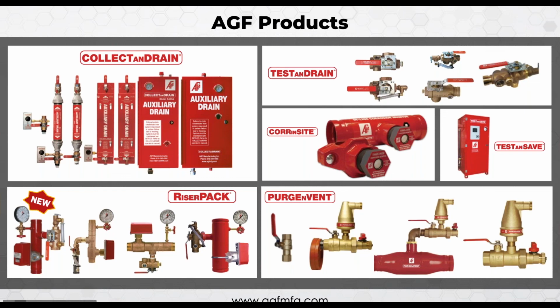Okay, thank you. The next question I have is, does the CorrInSite only show the corrosive elements within the pipe it's attached to, or can it detect within the whole of the system? So, to rephrase, what is the span of one CorrInSite unit? Well, typically, if I had a 5-story office building, I'm probably going to have 3 or 4 of these located. One by the inbound water supply, somewhere around the alarm valve. Maybe on floors 2 and 4 at the sectional floor control, and then maybe one towards the end of the system. That's going to give me good representative samples of both the quality of the pipe as well as the condition of the water in the system.